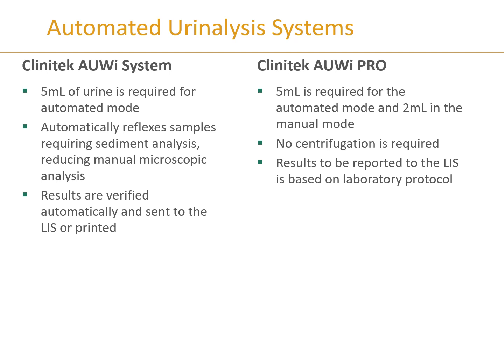Clinitek makes a variety of automated and semi-automated urinalysis systems. Two of their systems both require five mLs of urine. They can perform automatic reflex testing and automatic result verification — if results are normal, they auto-verify. A key advantage is that no centrifugation is required; you do not need to pre-centrifuge samples.